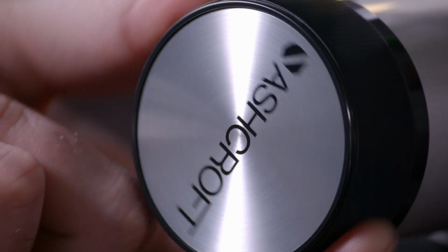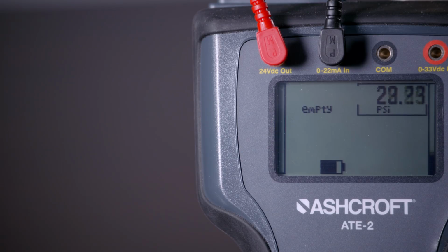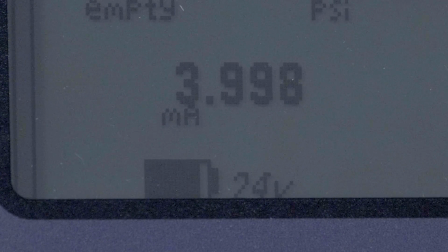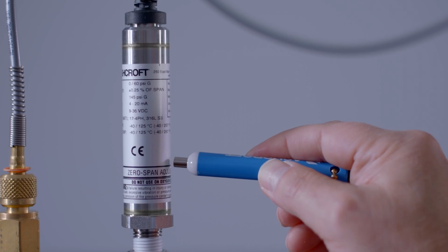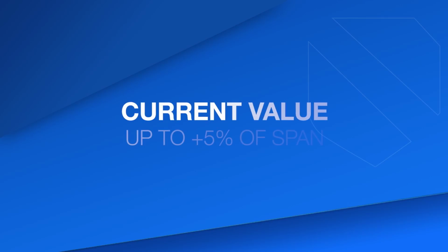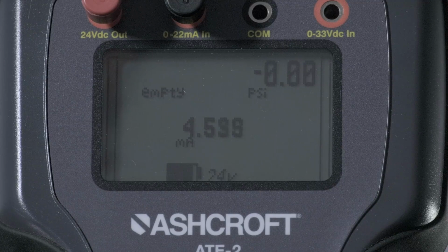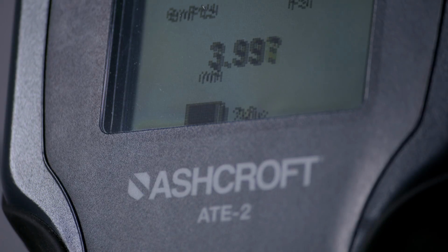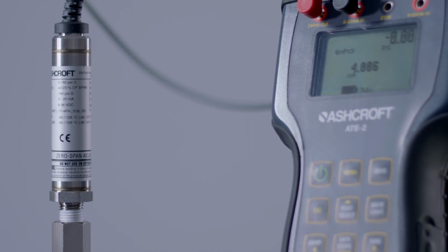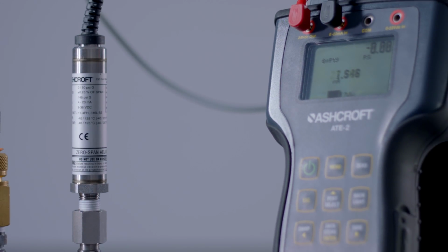Now, adjust the applied pressure to 0 and adjust the output to 4 milliamps. Like the span adjustment, the offset will increase from its current value up to plus 5% of span. Once the offset output has reached the max value, the offset will jump to minus 5% and continue to increase. Once the offset value is set, allow the ATE-2 to time out of calibration mode by waiting 30 seconds.